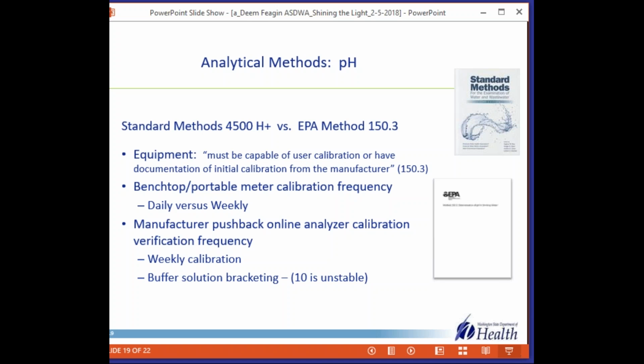Also, though, I'm wondering if you don't have a good sampling site or location for your probe, and it's hard plumbed into a pipe, and you have to shut down your operations to calibrate it, there is a huge barrier to doing it. So some of this could be driven by whether you have a good setup for your pH probe that allows you to calibrate. And if we raise that during the design, which we started to do, I think we can gradually get to the place where it's easy to do the grab sample verification.